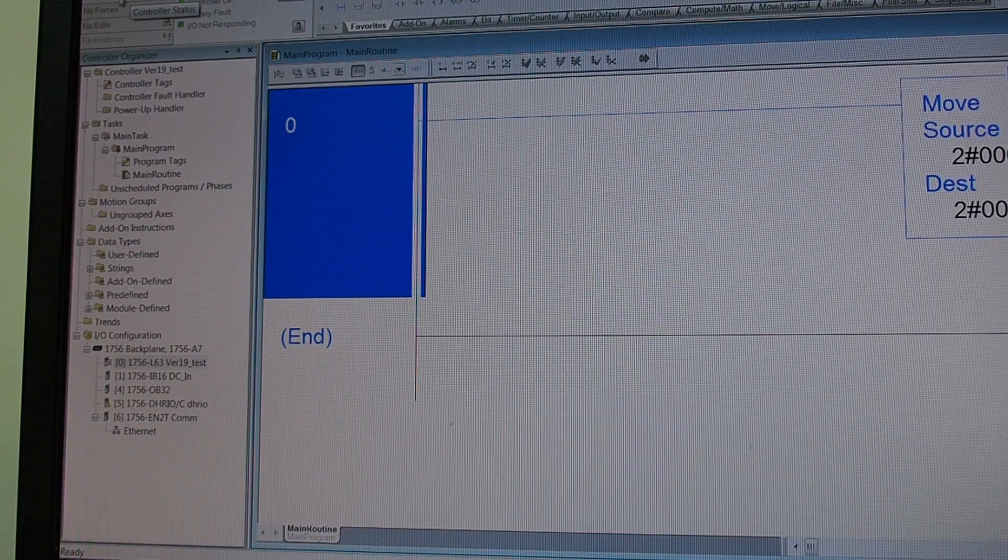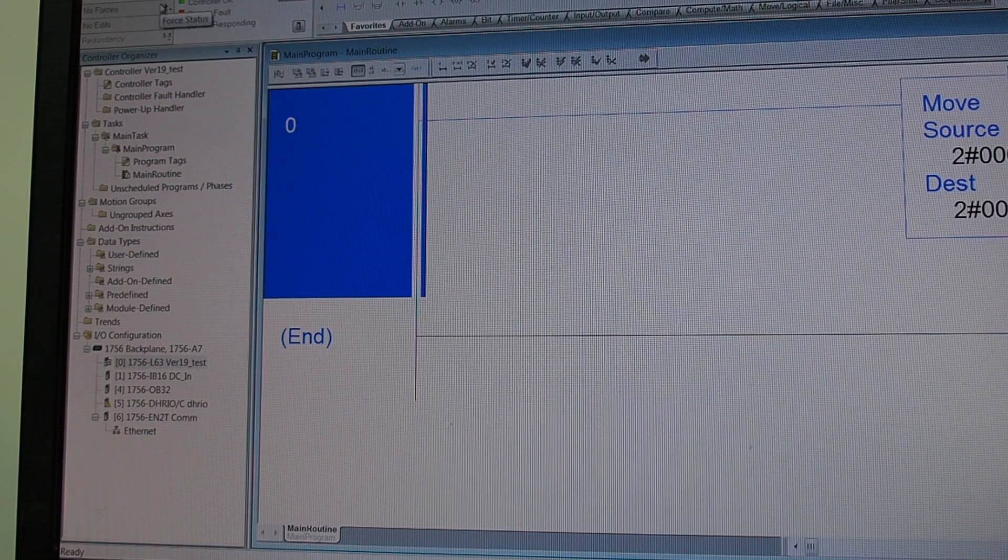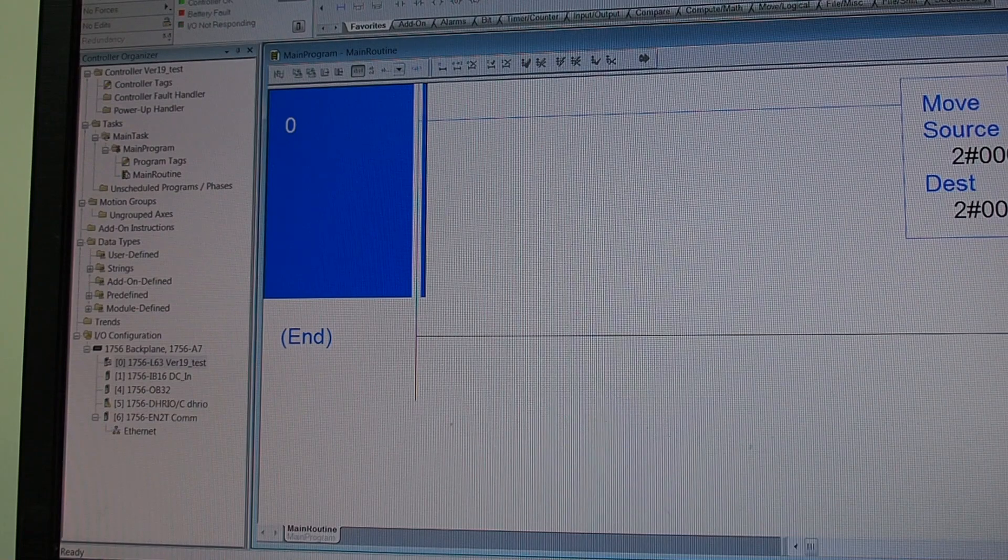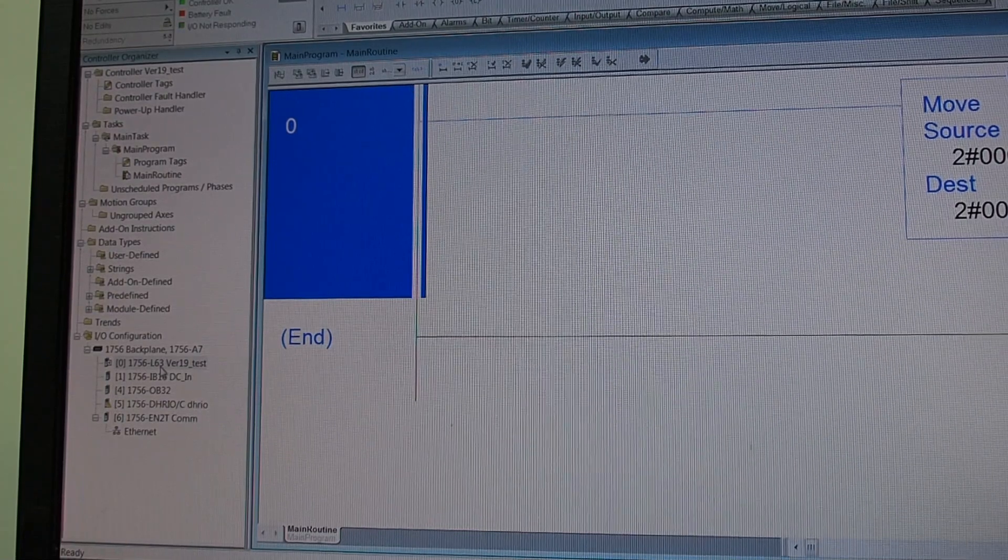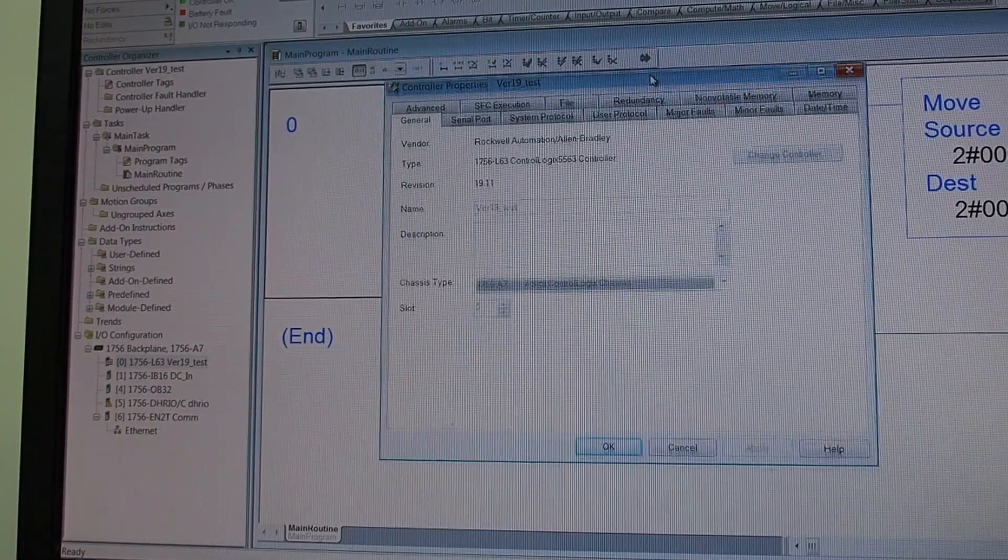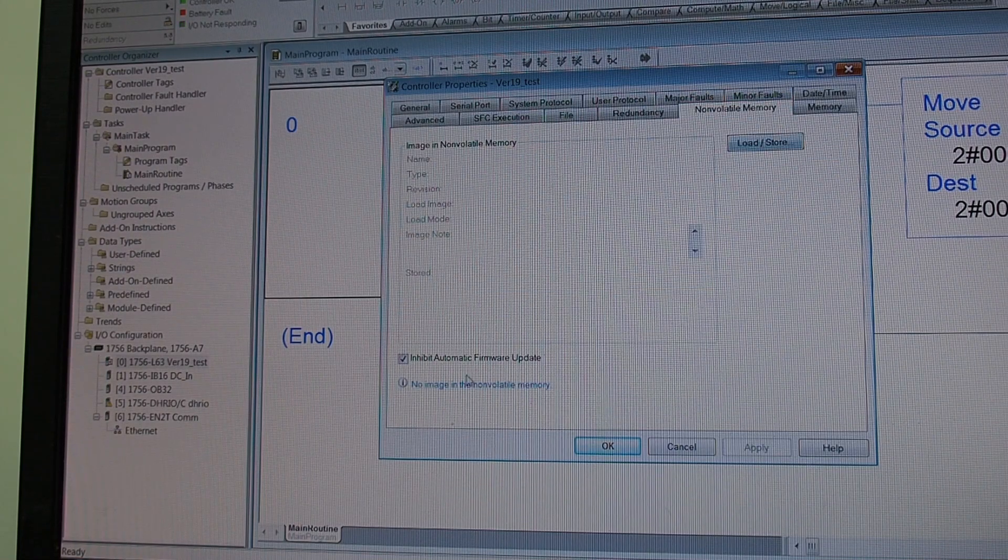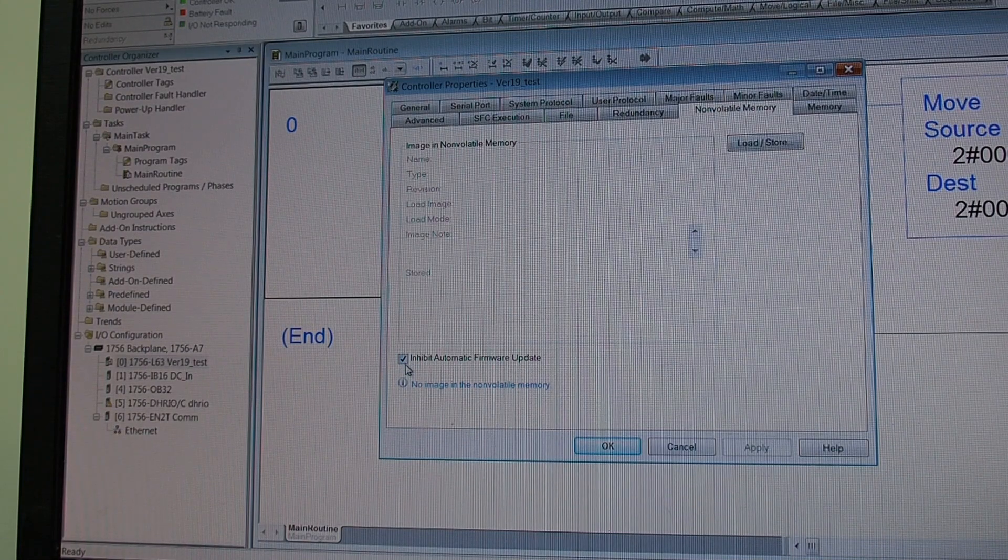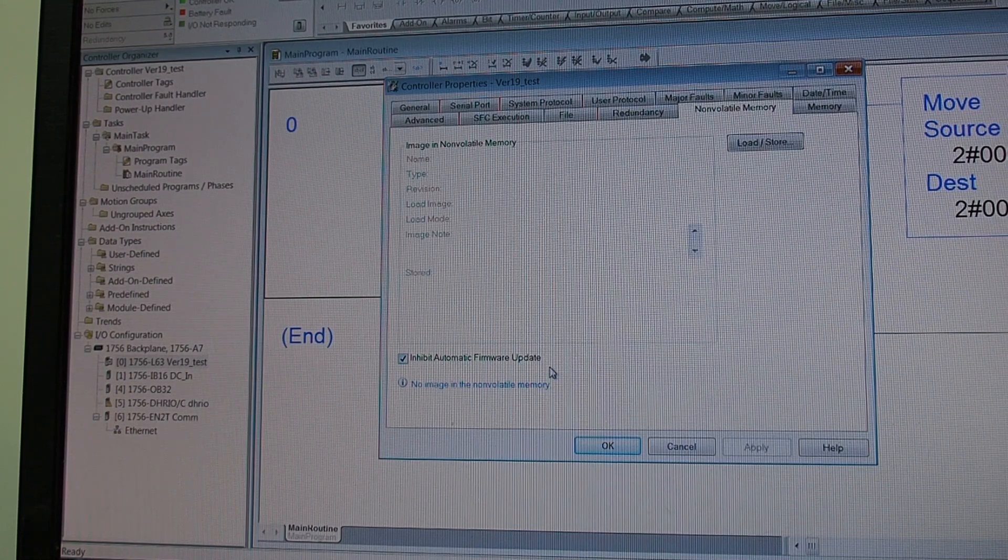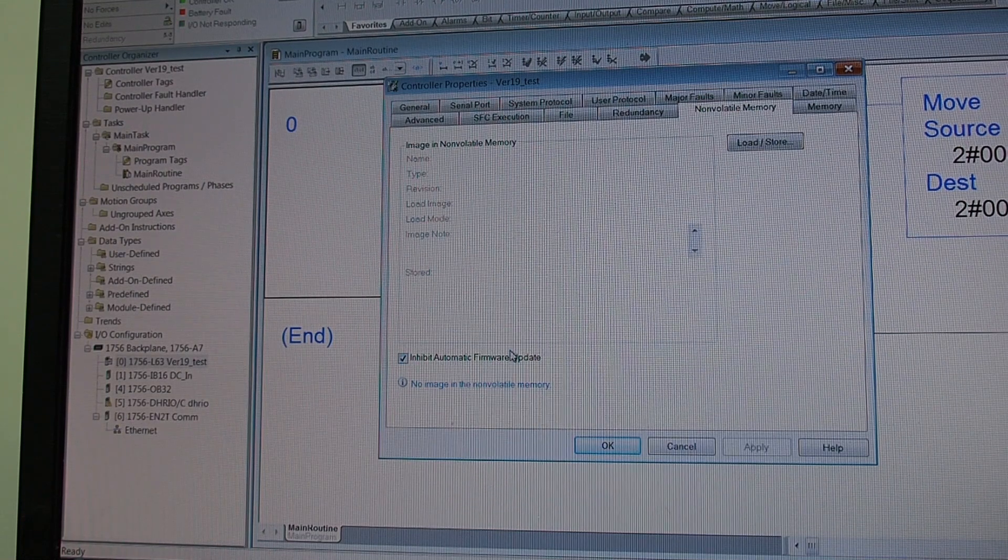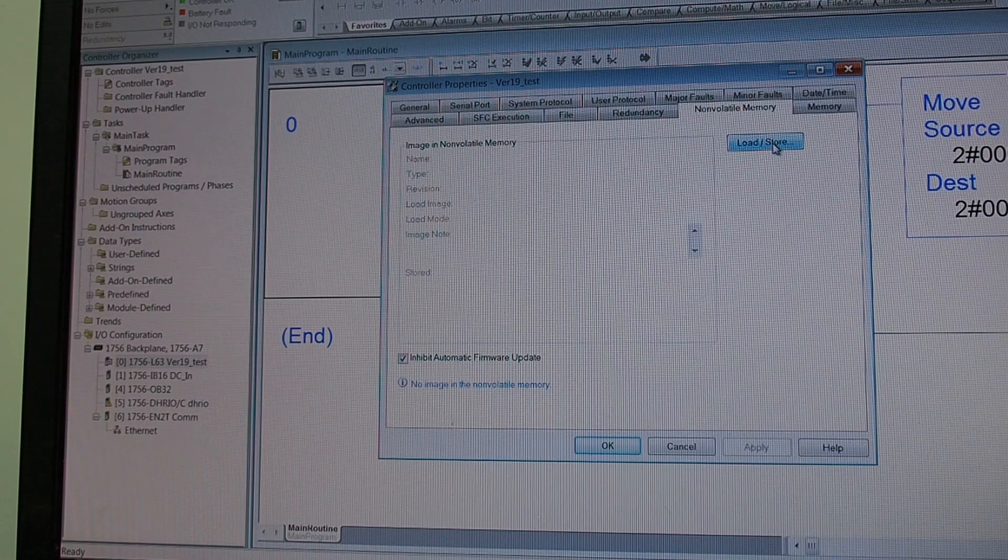And again we are in program mode as you can see here in the upper left hand side because our key switch is in program. If we go into the processor tab, into the memory, okay the first thing that we want to do is down here on this side, inhibit automatic firmware update. You want to keep your firmware at the same level it's at right now because that's what you're working with.